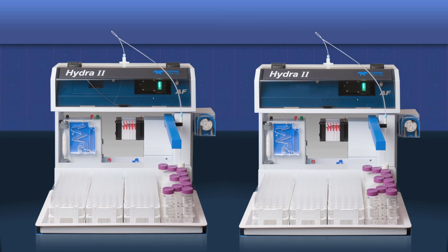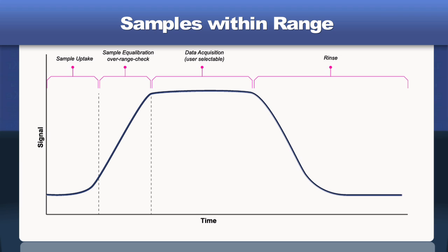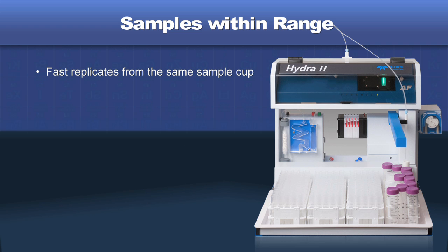The Hydra 2 AF and AF Gold differ in the way they take measurements. The analysis cycle for a typical sample involves a short period of time for sample uptake, sample equilibration, data acquisition, and rinse. Unlike conventional systems that consume all of the material in the sample cup, the Hydra 2 AF is able to quickly conduct multiple replicate analyses from the same sample cup. This approach ensures high measurement quality and allows the operator to reanalyze the sample if needed.